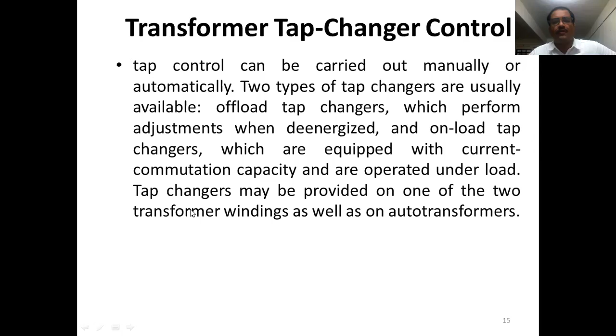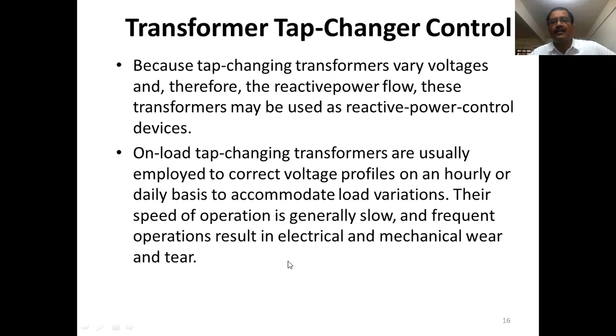Tap changers may be provided on one of the two transformer windings as well as on the autotransformer. Tap changing transformer control varies the voltages and therefore the reactive power flows. These transformers may be used as a reactive power control device. On-load tap changing transformers are usually employed to correct the voltage profile on an hourly or daily basis to accommodate load variation. Their speed of operation is generally slow, and frequent operation results in electrical and mechanical wear and tear.